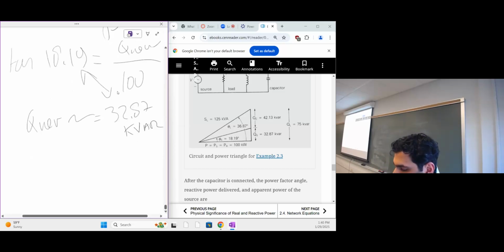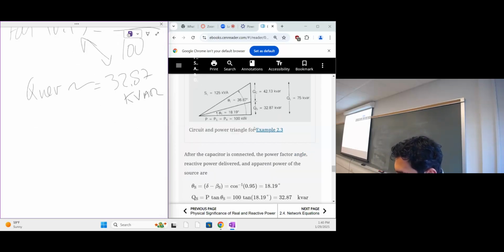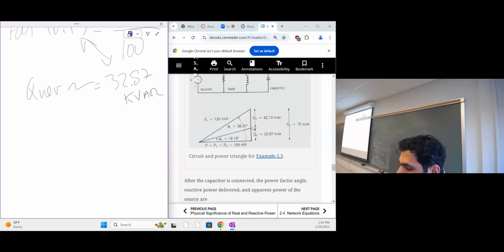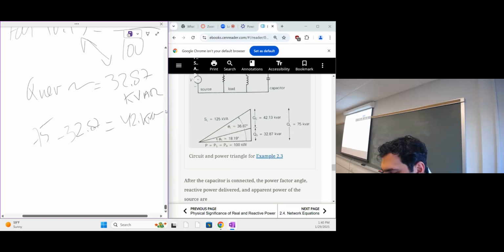So effectively, this is how we should do it. So we'll be removing actually from the 75 we remove those 32.87 kilovars, then we see that we reduced our reactive power by 42 kilovars to obtain a power factor of 0.95, okay, which is very good.